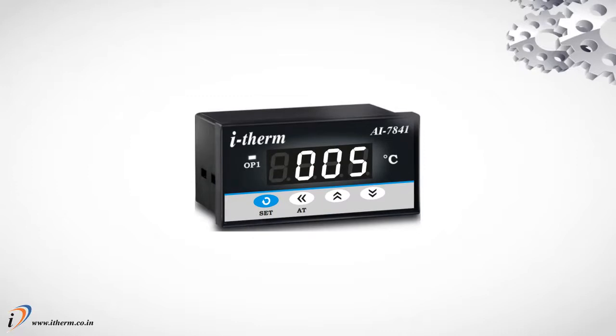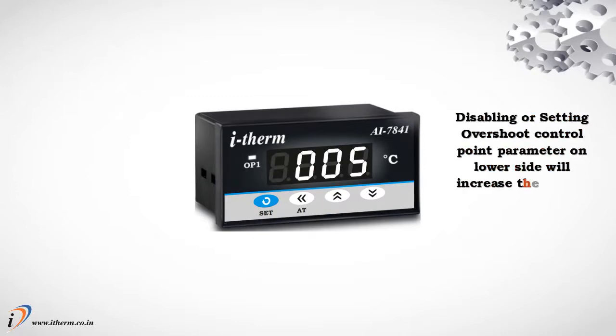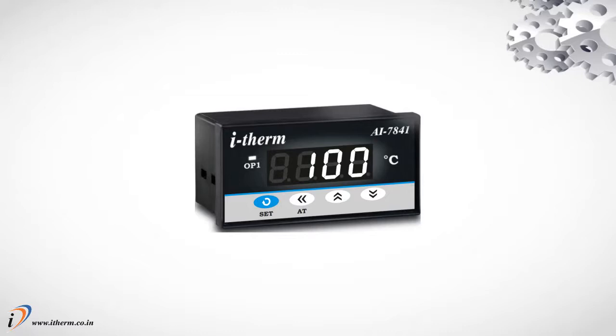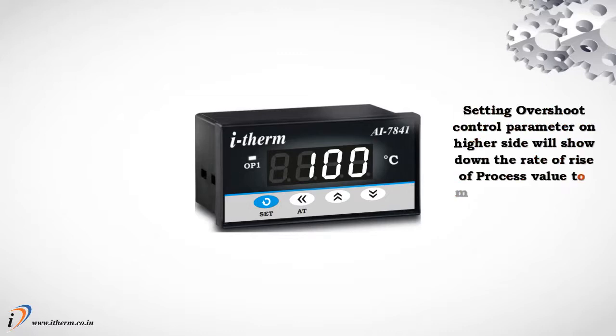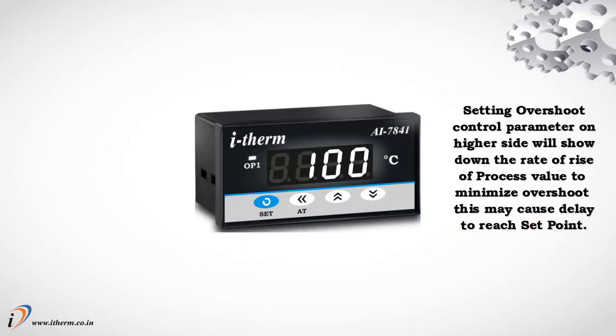Disabling or setting overshoot control point parameter on lower side will increase the rate of rise of process value, which may cause overshoot. Setting overshoot control parameter on higher side will slow down the rate of rise of process value to minimize overshoot. This may cause delay to reach set point.